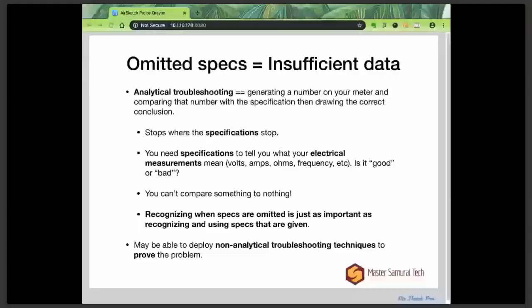In analytical troubleshooting, your troubleshooting stops where the specifications stop. Because you need specifications to tell you what your electrical measurements mean, whether you're dealing with volts, amps, ohms, frequency, whatever — in other words, is it good or bad. Without a spec to tell you that, you can't do analytical troubleshooting.